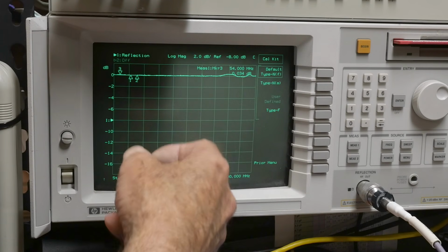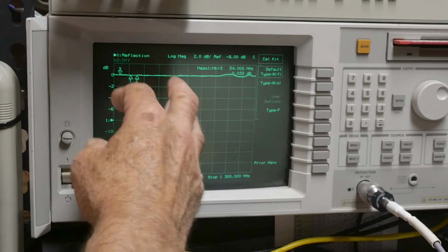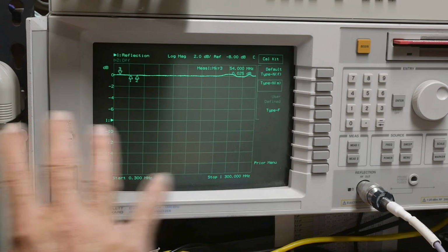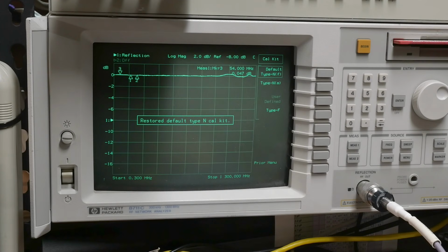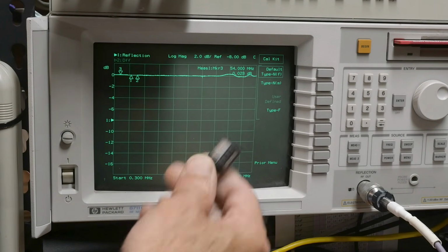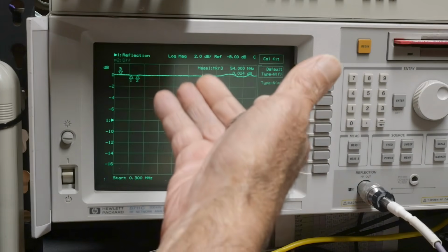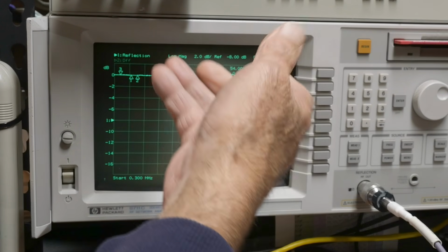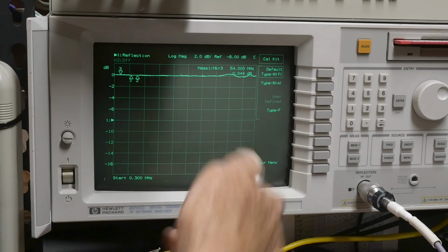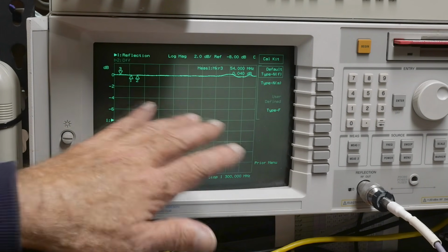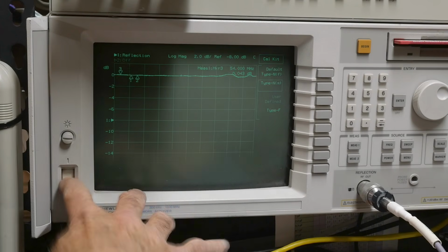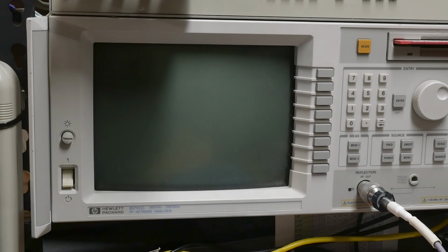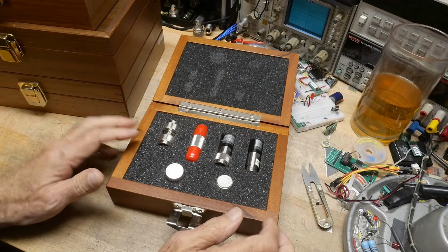If you want to do a generic calibration, then you hit the type N, which basically ignores any cal data. So the default N-type cal kit, these calibration kits, like I just showed, they will have a particular inductance and capacitance and variation versus frequency and stuff, and the machine knows all of that. And so when you use these kits that are privy to this particular machine, it will use all that information. And by typing this in, it ignores all the information. So I need to figure out which cal kit this one shipped with, and maybe it's one that I have here.